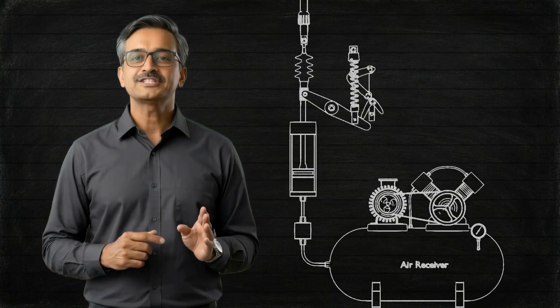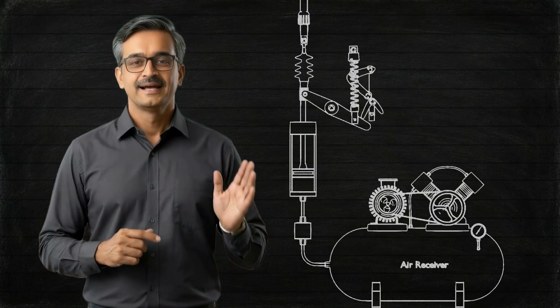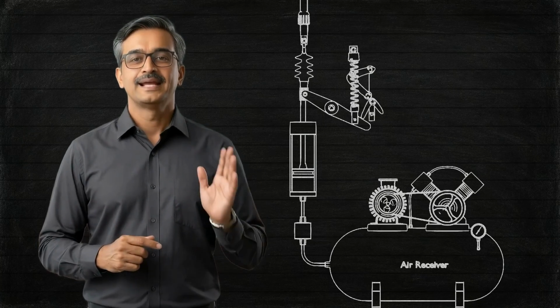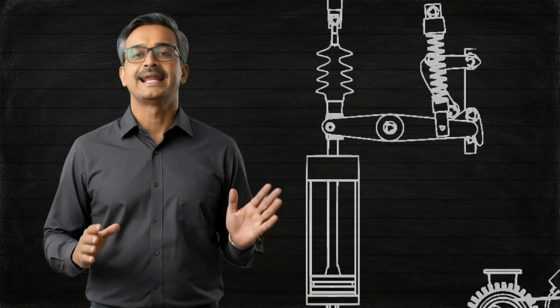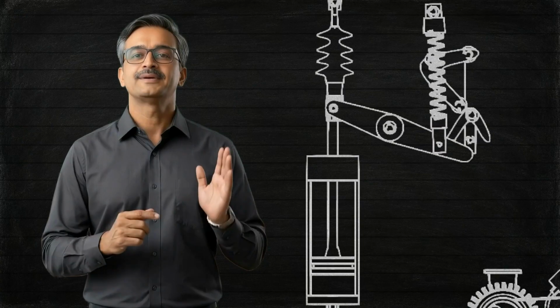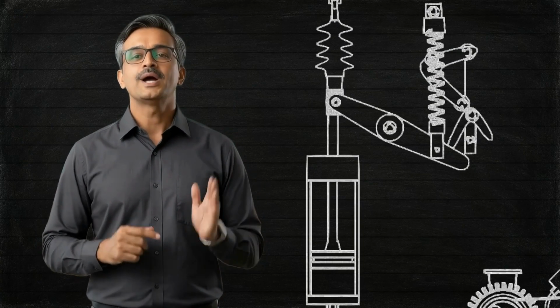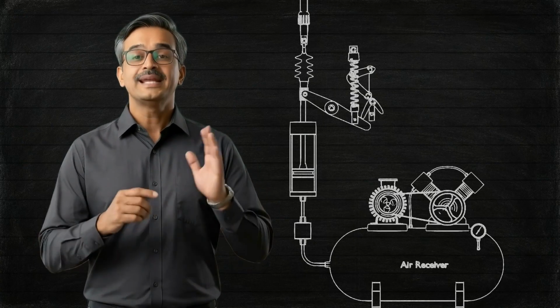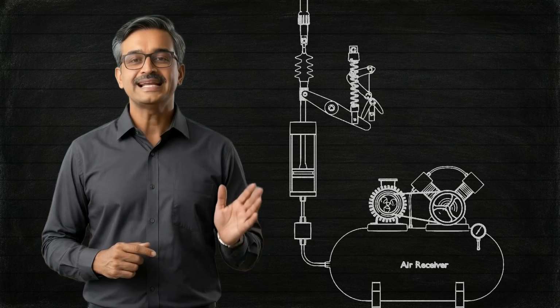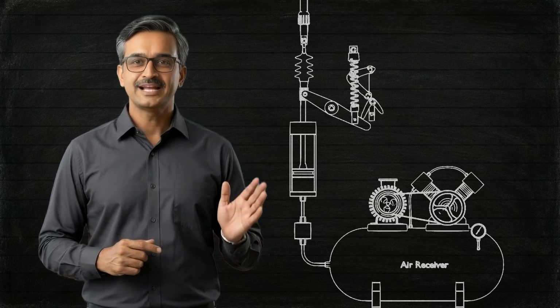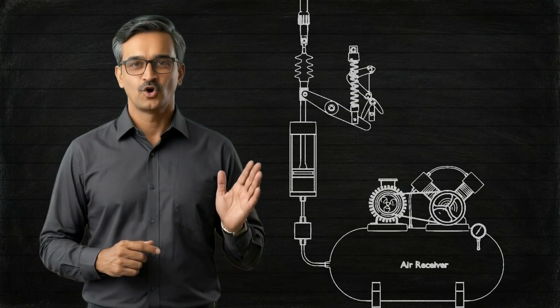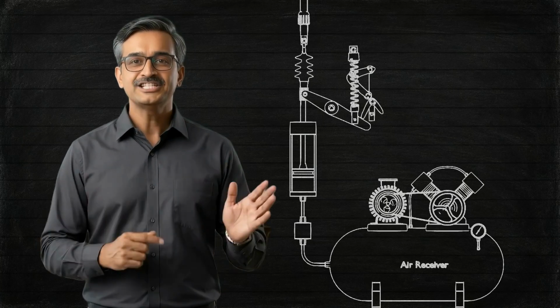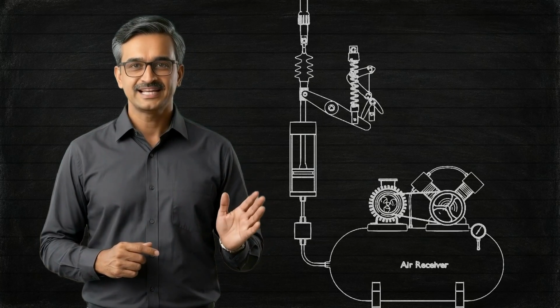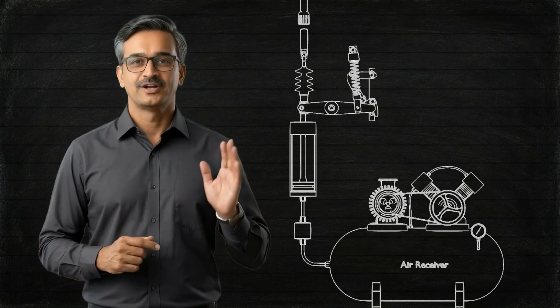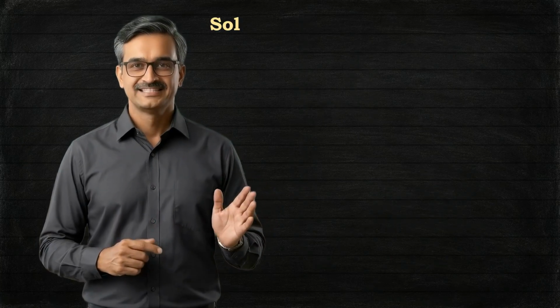But something very interesting happens during this closing movement. As the piston travels, it is not only closing the breaker. At the same time, it also compresses the opening spring. So immediately after the breaker is fully closed, the opening spring becomes fully charged. In other words, the energy required for the next opening operation has already been stored in the opening spring. When a trip or open signal is sent to the trip coil, the trip coil is a small electromagnet. This electromagnet releases the latch holding the compressed opening spring. As soon as the latch is released, the spring expands rapidly. The linkage moves. The moving contact separates from the fixed contact. Hence, the breaker opens.